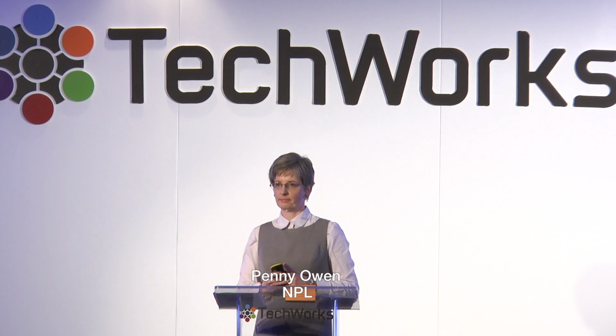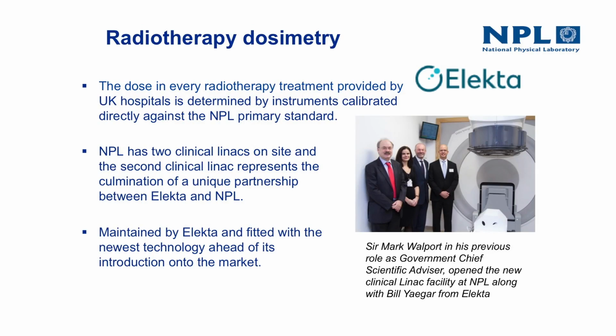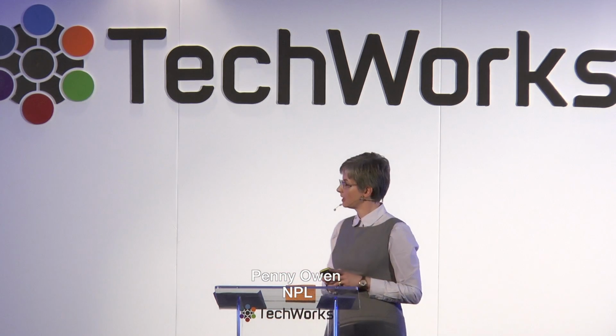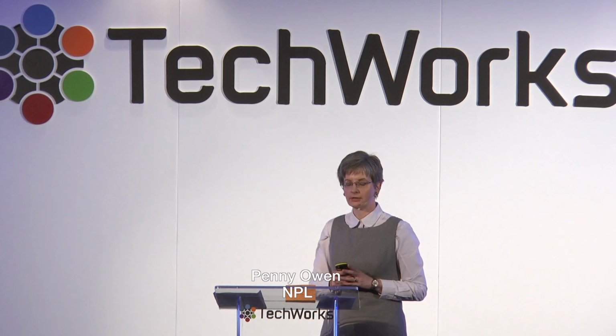If you are unlucky enough to need radiotherapy, I certainly recommend that you come and have it in the UK. And the reason is because over the last 10 years in the UK, we've established a traceable system of calibration and audit across UK hospitals. What that means is that linear accelerators across the UK are calibrated to the primary standard that we hold at NPL. We send out phantoms.